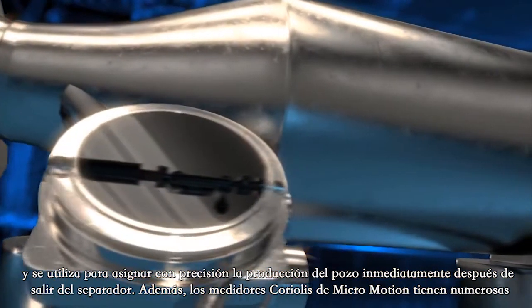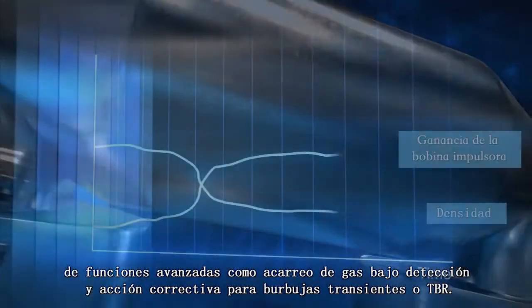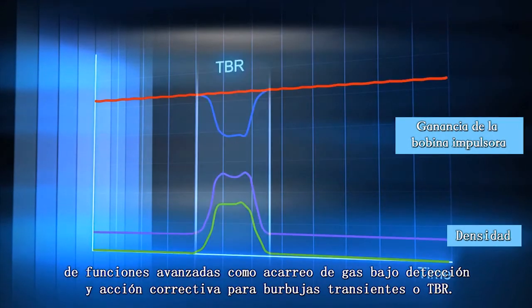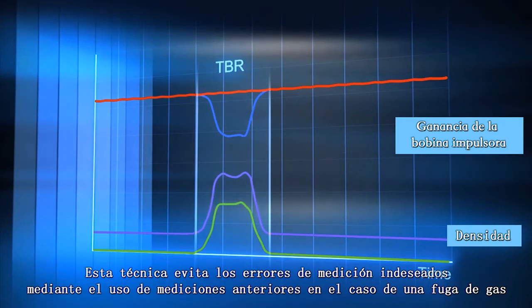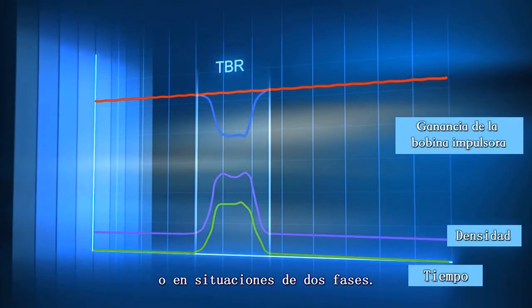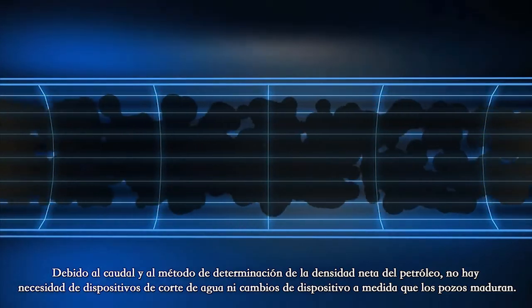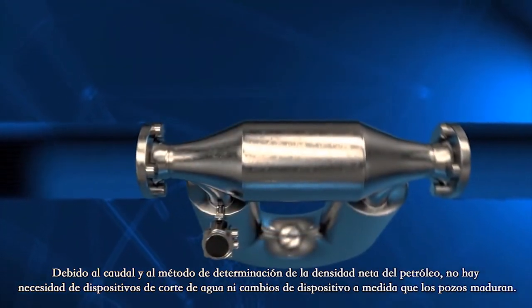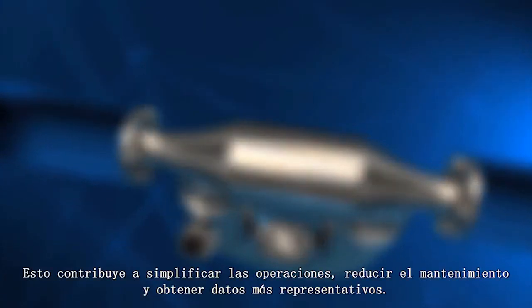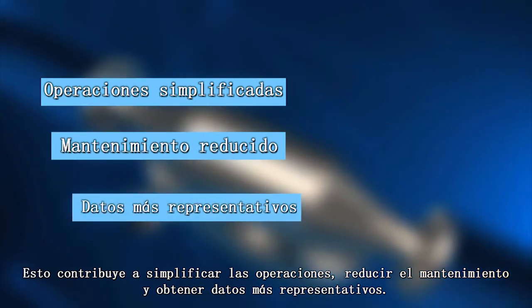In addition, Micro Motion Coriolis meters have a number of advanced functions such as gas carry-under detection and transient bubble remediation, or TBR. This technique prevents unintended measurement errors by utilizing previous measurements in case of gas breakout or in two-phase situations. Because of the flow rate and net oil density determination method, there's no need for water-cut devices or device changeover. This contributes to simplified operations, reduced maintenance, and more representative data.